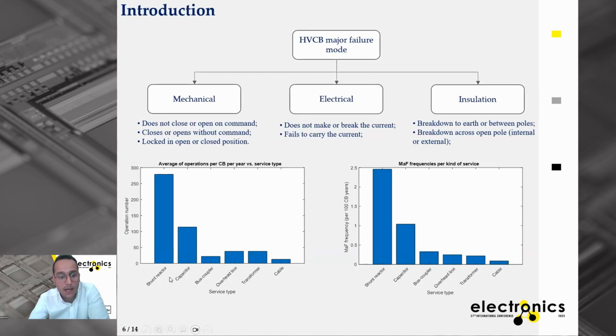In the figure on the left-hand side, based on the statistics, we can see that the service type, or the place where the high voltage circuit breaker is going to be used, is important for the number of operations it's going to have. By operation, I mean close and open operations. If we use circuit breakers for shunt reactors, we would have more operations than when we are using them for cables or transformers.